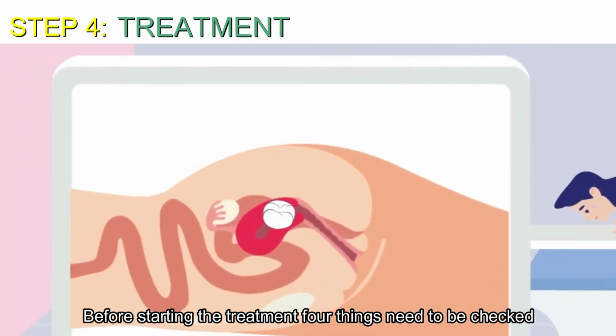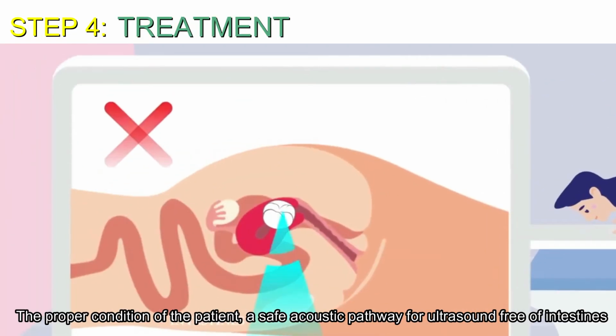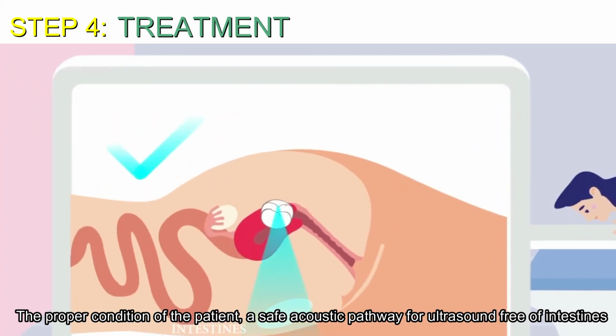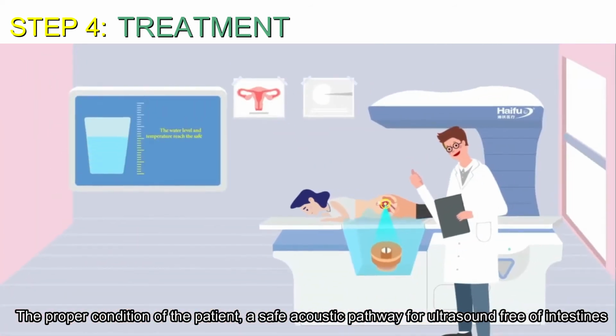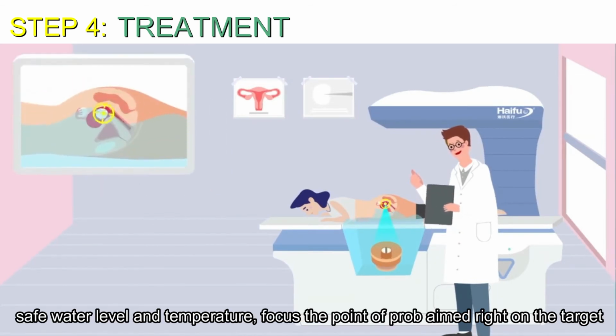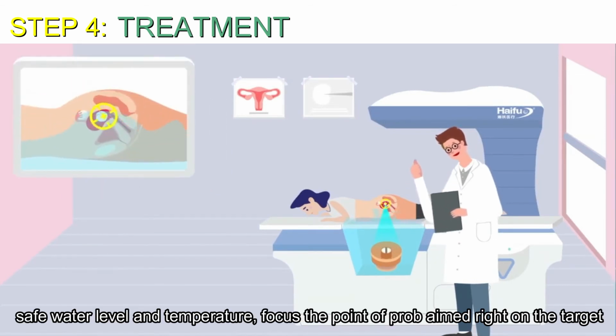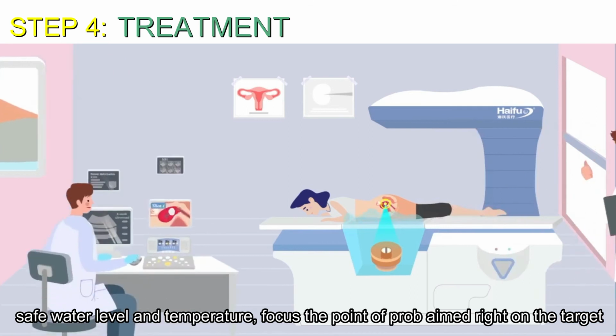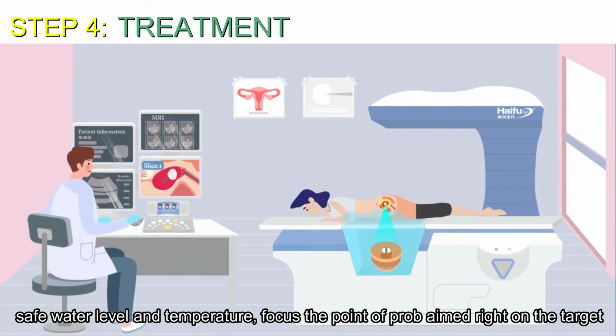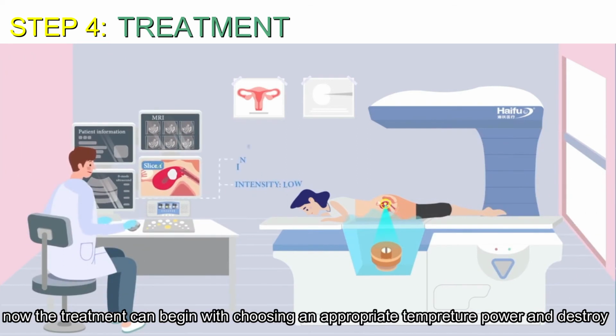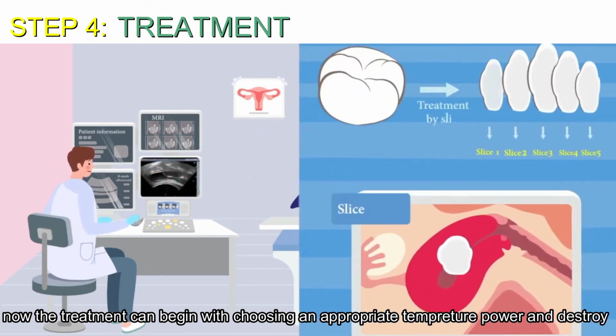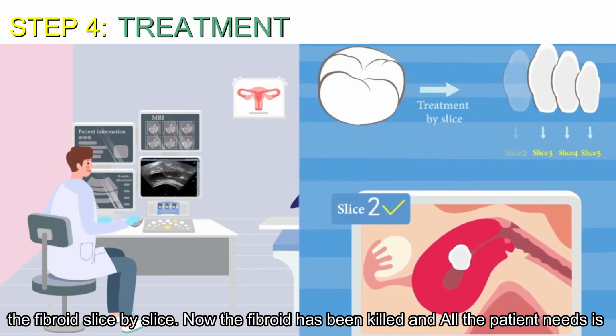Step 4, treatment. Before starting, four things need to be checked: the proper condition of the patient, a safe acoustic pathway of ultrasound free of intestines, safe water level and temperature, and the focus point of the probe aimed right on the target. Now the treatment can begin, choosing appropriate temperature and power to destroy the fibroid slice by slice.